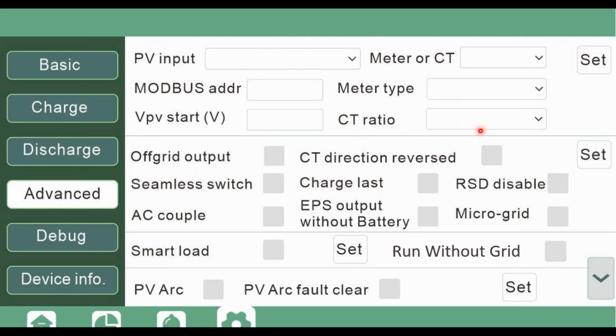Right? Here we set the CTs as we mentioned before. And then here we enable off-grid output. So the inverter does go in backup mode. Seamless switch: when the inverter transitions from a grid outage, it will switch to backup in less than 20 milliseconds.